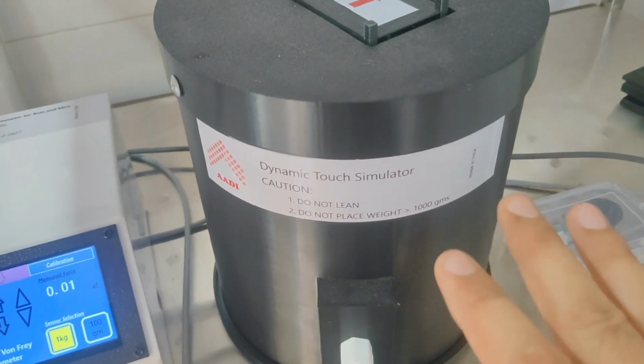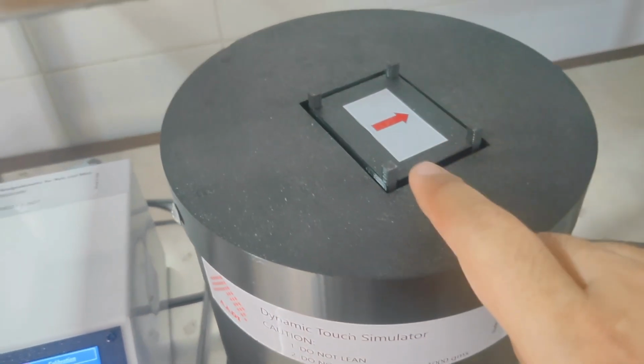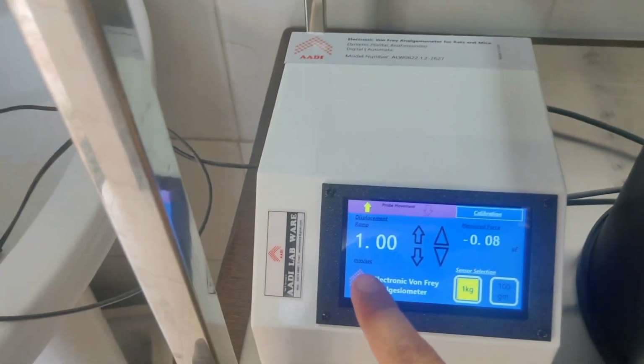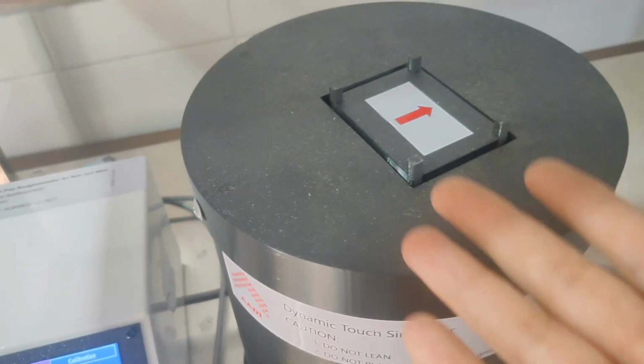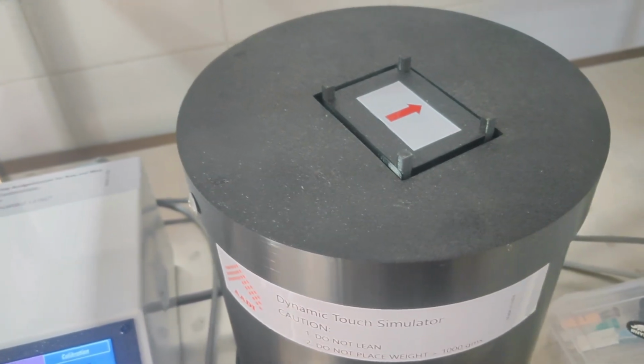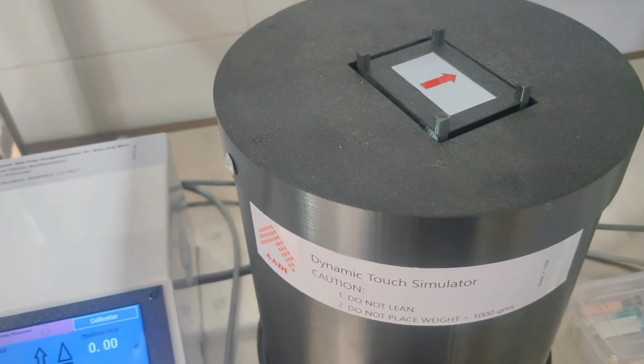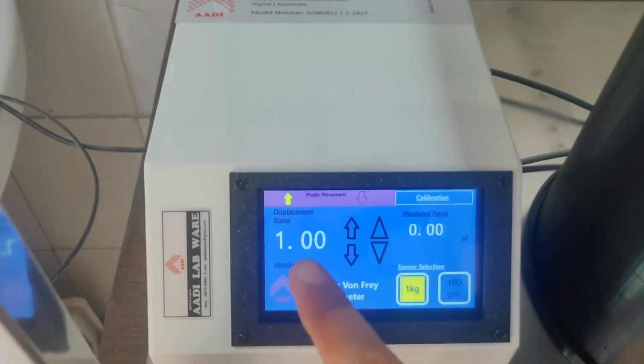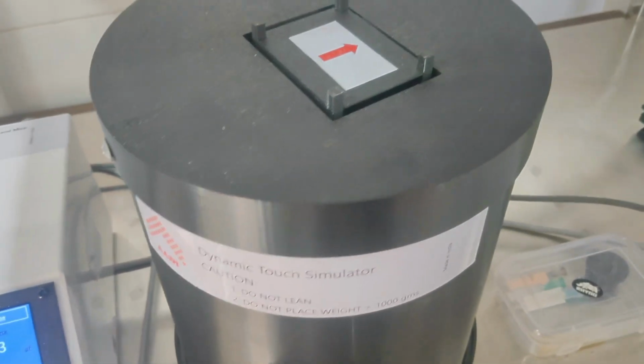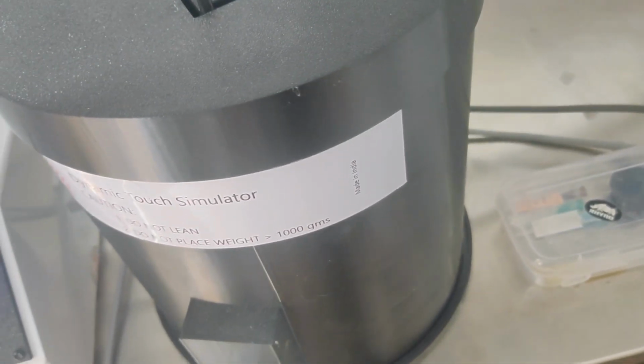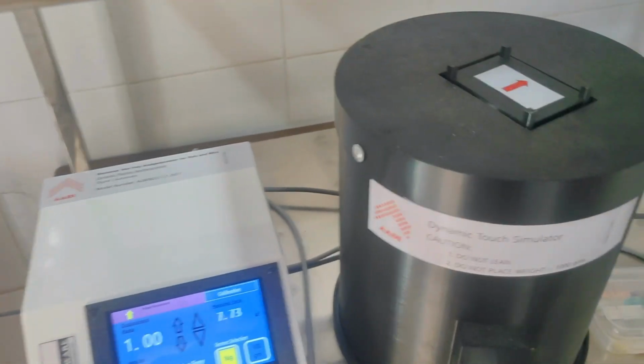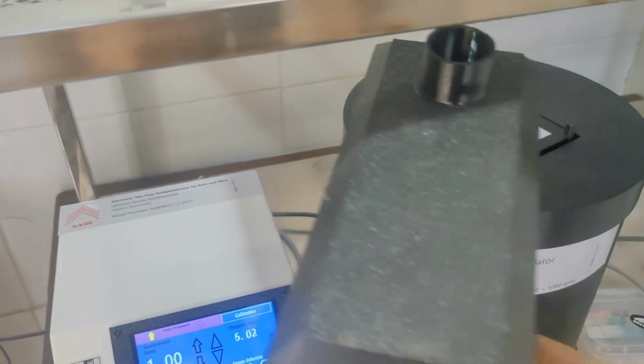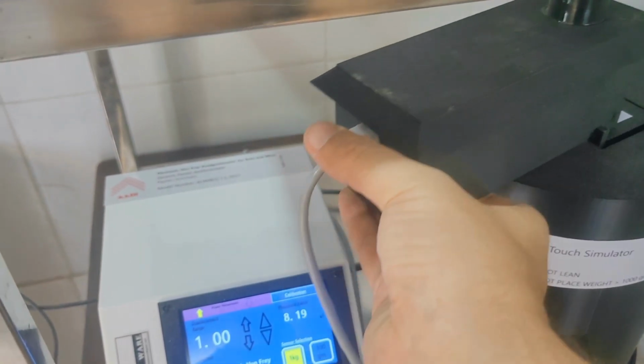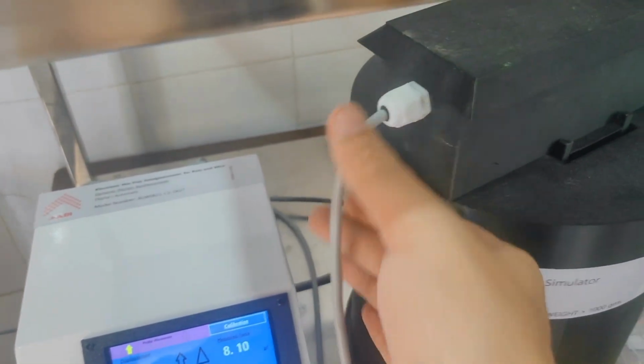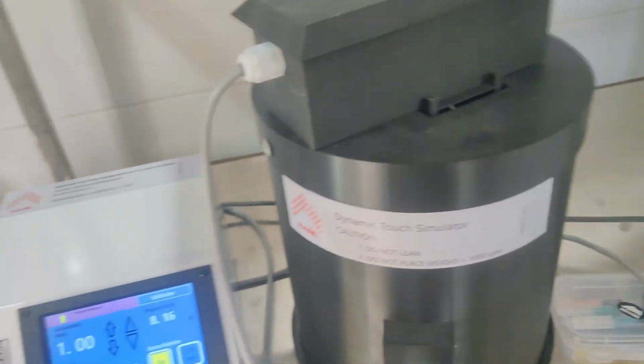Now this is the main part of the instrument. This is a dynamic touch simulator. What this does is that we have a platform here, and this platform, based on the speed we have decided here, can be raised up or descended down at that rate of speed. Suppose we want a very gentle touch on the plantar surface, we will set the speed here, let's say about 1 mm per second. Let us now place the transducer here. We can place the transducer through the guides, and the transducer is now ready to work.